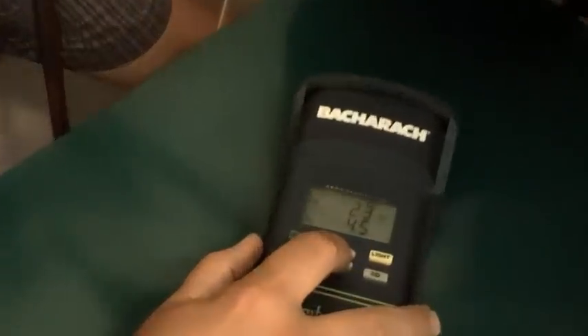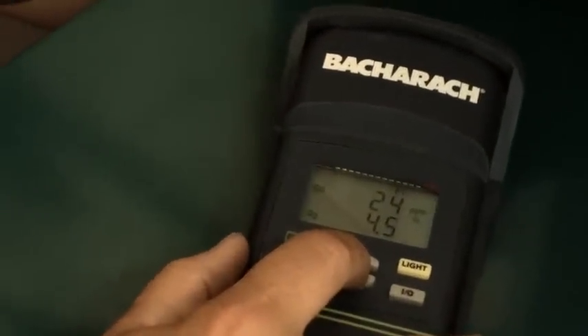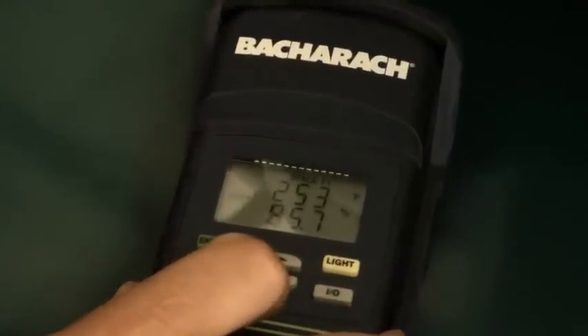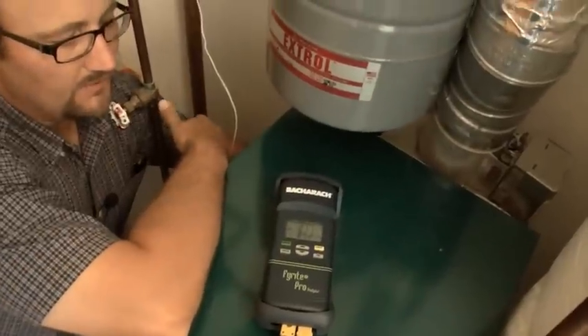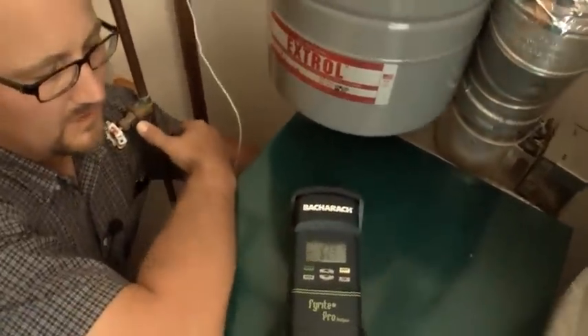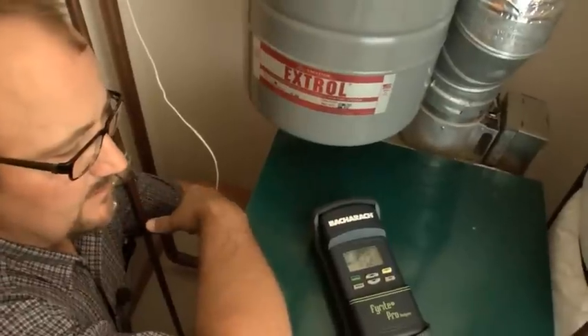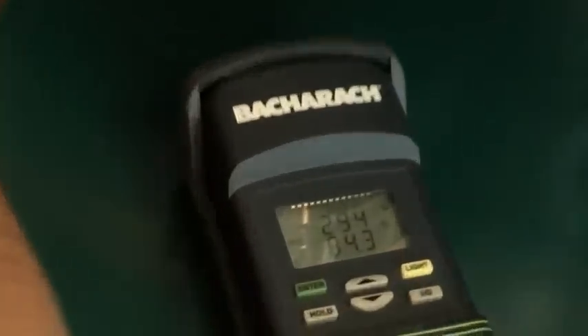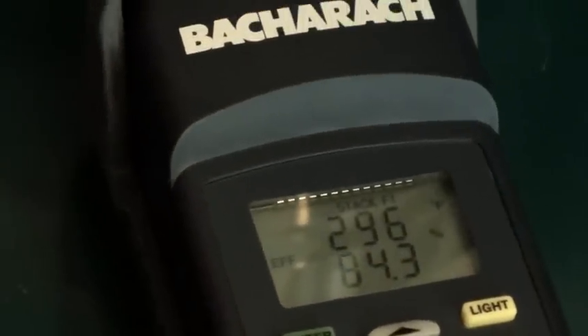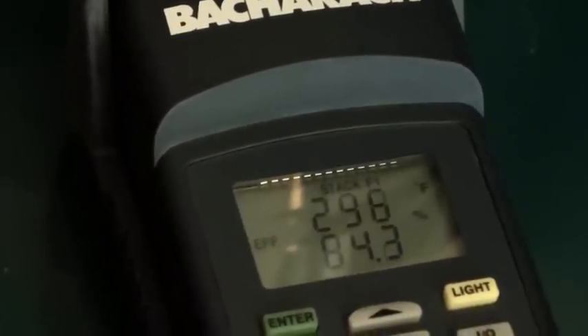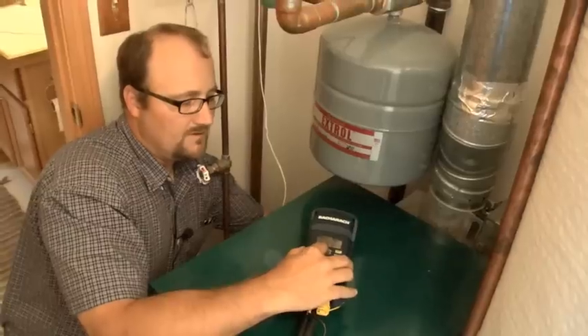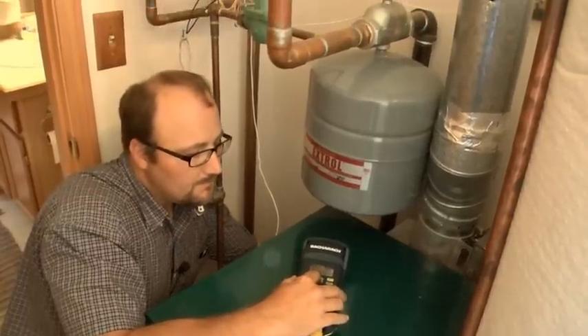We have a good burn, plenty of oxygen, proper amount of fuel. We look at our efficiency, we're running 85.8. This thing's been running a little while now, but as it heats up, the efficiency does start to drop. So it looks like it's going to end up hitting in that 83-84% efficient area.